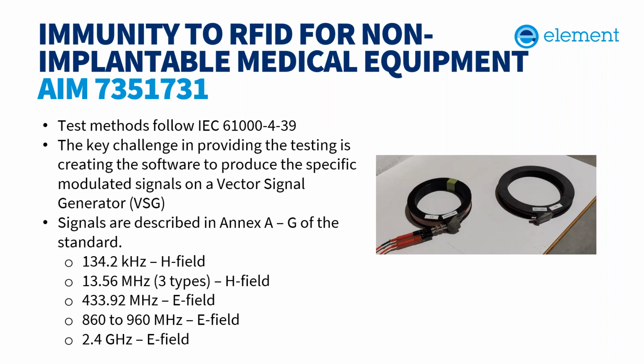And this is not just a test to do a test. There is a known issue, a documented issue from a few years back, where magnetic instrument mats, which are being used in an operating room, were interfering with RFID tagged surgical sponges. So they've got the RFID for the surgical sponges to track what's going in and out of the patient during surgery, which can be health critical. And the RFID was being screwed up by a magnetic instrument mat. So this is something that definitely is a concern. It can happen, and that's why we've got the test.